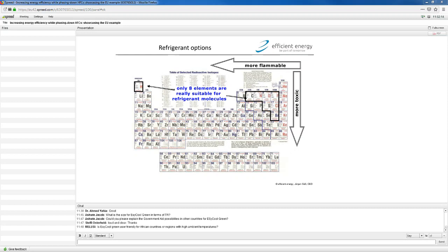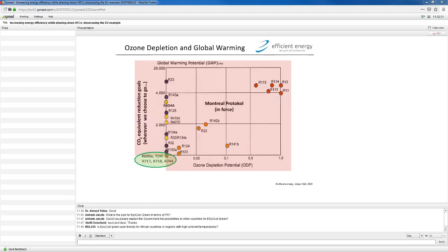You can definitely say, or that's for sure, there will be no other solution than what we see today, and all the rest is more or less politics, or let's say lobbying. If you look at the refrigerants and ozone depletion, then we have Montreal Protocol which is in place, and that requires ozone depletion potential zero, which means we are on the axis where ODP is zero. And then the next question is how far do we want to go down in global warming potential.